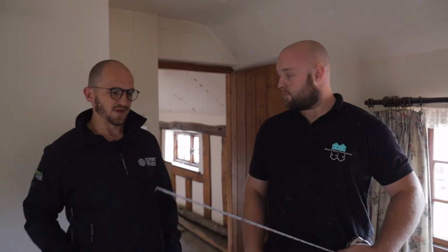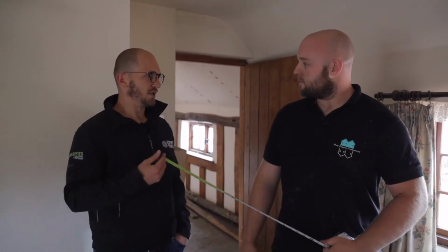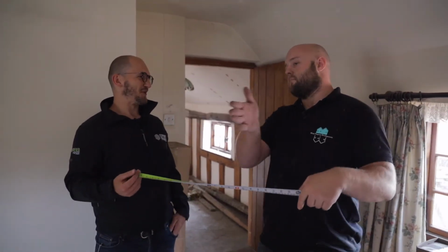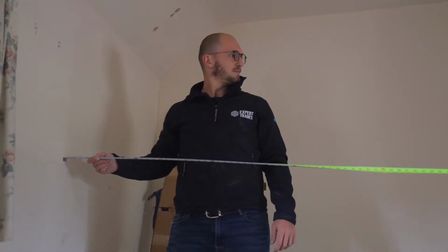But to get that actual size, we've got to work out the room volume and how much heat loss the individual room is going to lose. So what we've got to put back into it is going to be that size of the radiator. Perfect. This is the stuff that, as a homeowner, generally, we just think a radiator is a radiator. So we're going to measure the length, and then the width, and then the height.